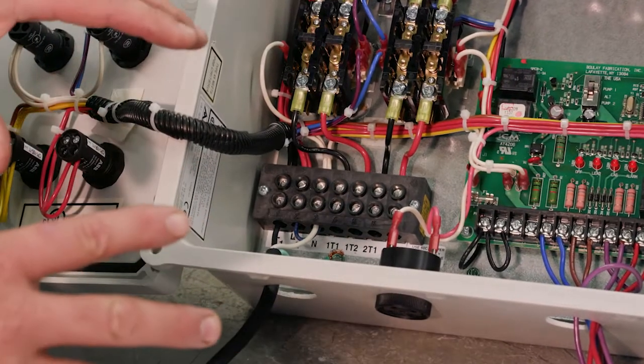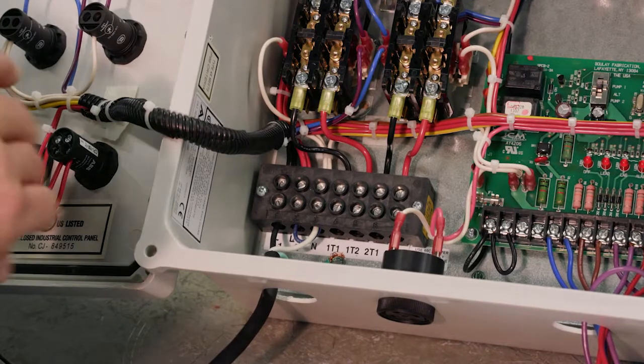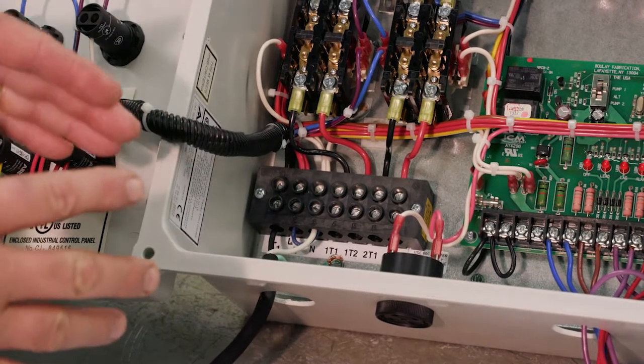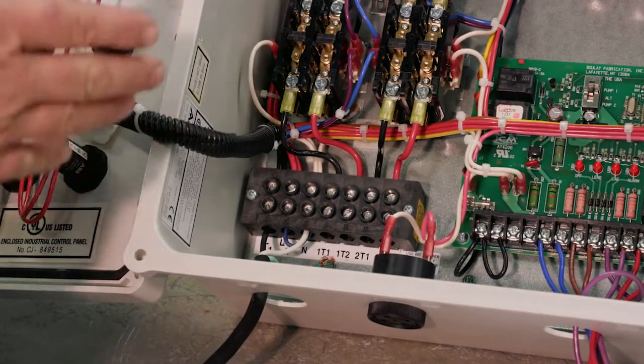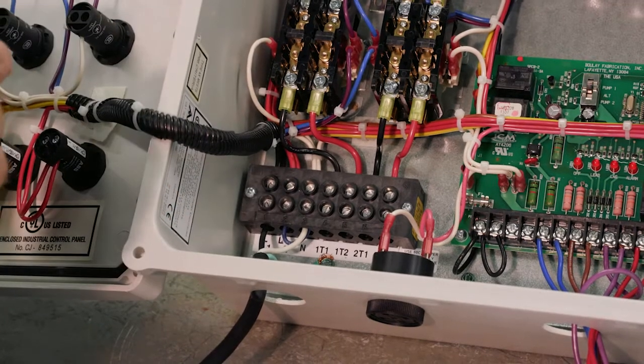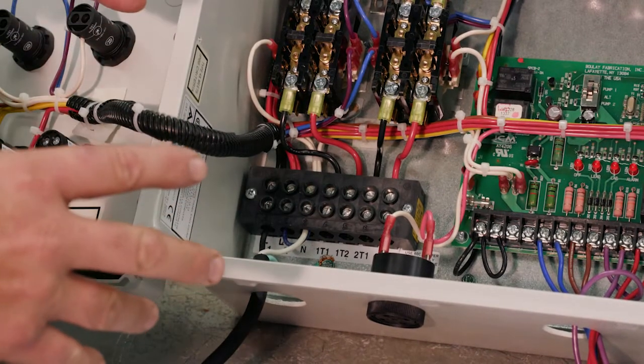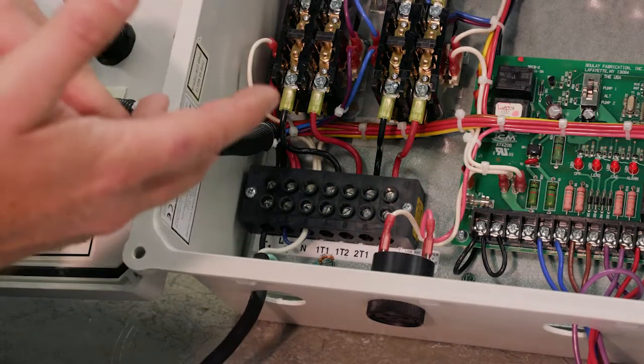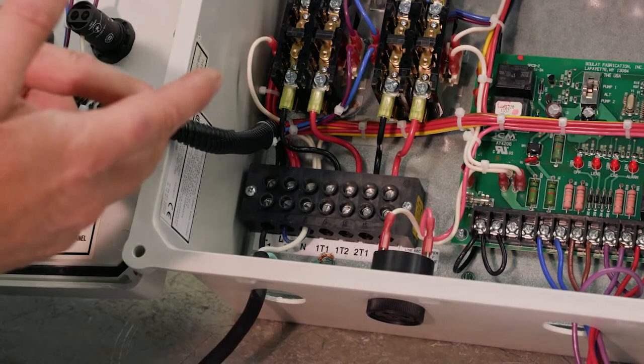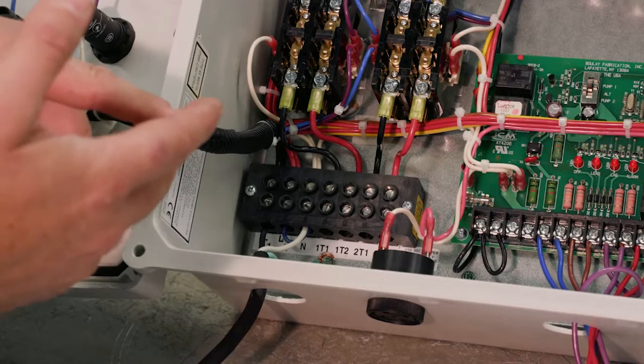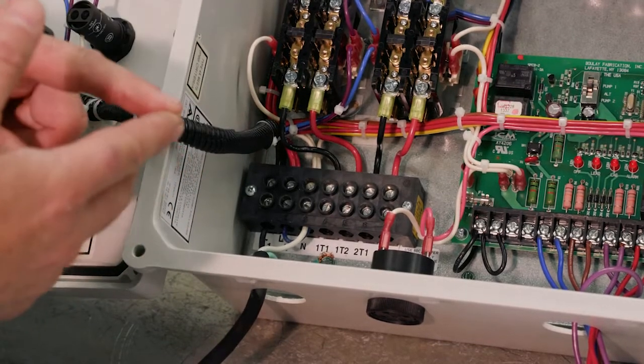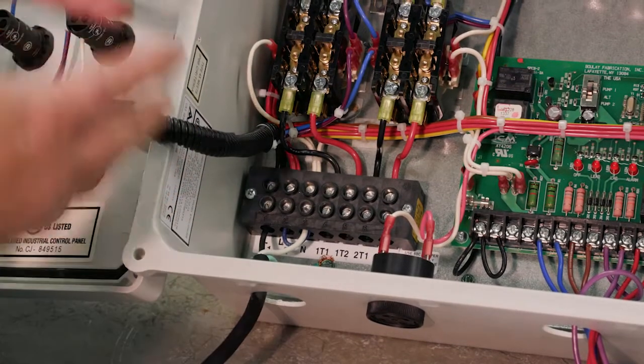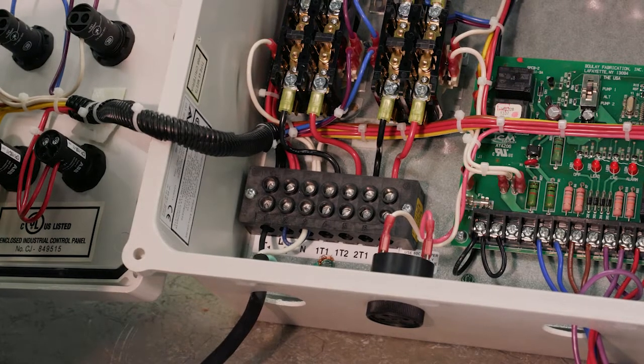So if our panel isn't working, it could be because we don't have a neutral, whether that's with 115 and we didn't put a jumper in or with 230. Because with 230, if you just have two hots and a ground, then it's not going to work because we need two hots, a neutral, and a ground. So this panel has to have a neutral.